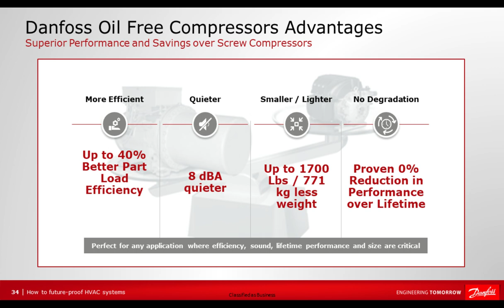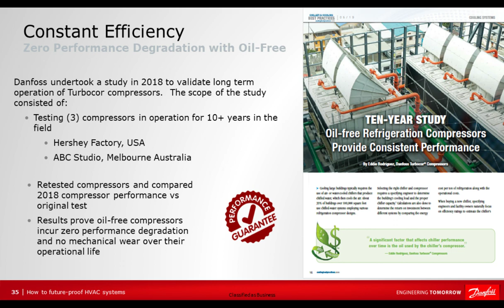One of the things we've done with the Turbocor compressor is we took some compressors that have been in the field over 10 years. We took those compressors off the chiller they were installed on, brought them back to the Danfoss Turbocor factory, and measured the same performance to the same standards that we shipped them at 10 years ago, and we saw zero change, zero degradation in performance. We plan to extend this study to include more compressors, but the key thing there is you had consistent performance over time. It's one of the things that Drew talked about that people will be looking at in the future: do they maintain that same efficiency and that same capacity over time as the system is installed.